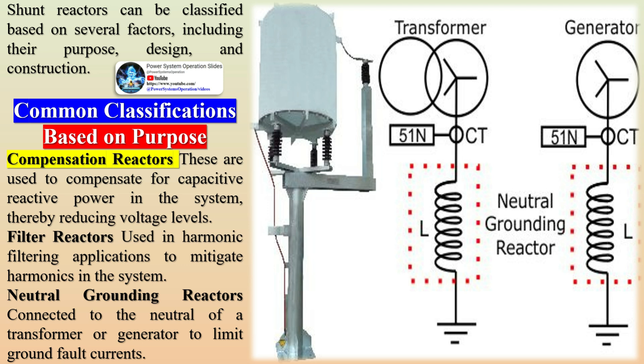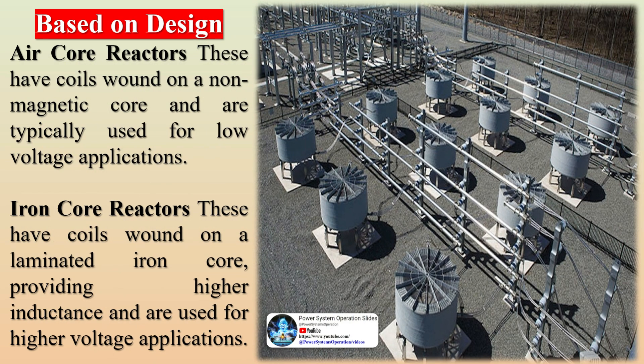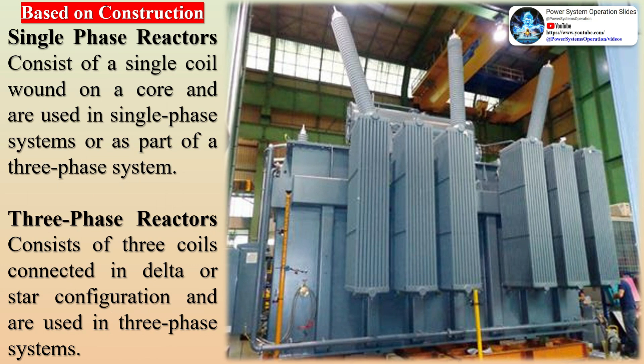The electromagnetic operating principle of a shunt reactor can be explained as follows. When a shunt reactor is connected to a power system and voltage is applied, an initial surge of current flows into the reactor — this is called the charging current — which creates a magnetic field around the reactor coil. The changing current (di/dt) generates a changing magnetic field which, according to Faraday's law of electromagnetic induction, induces a voltage in the coil in the opposite direction to the applied voltage.